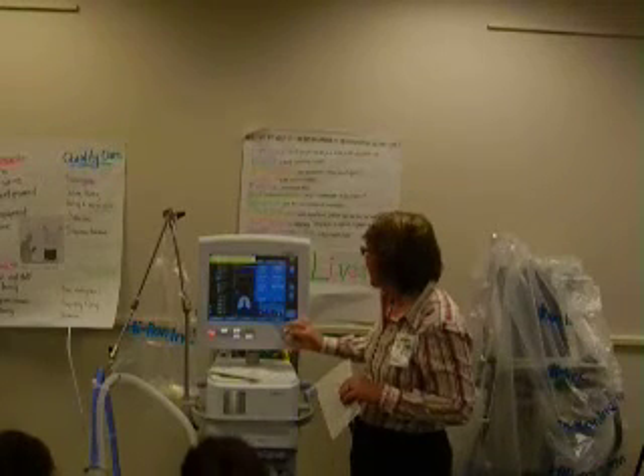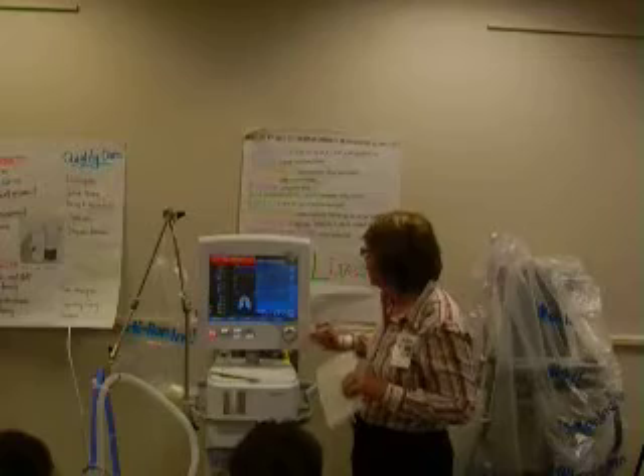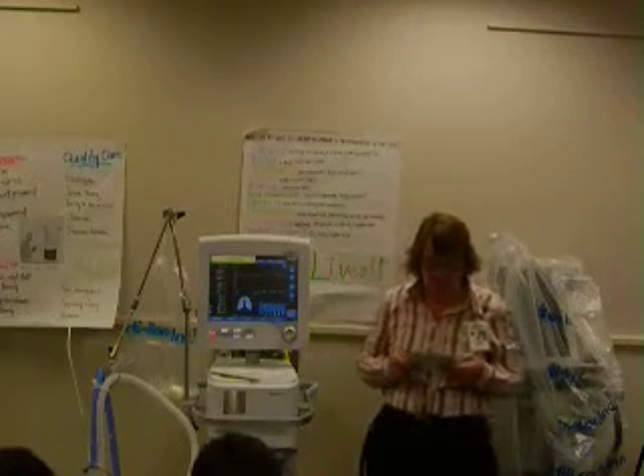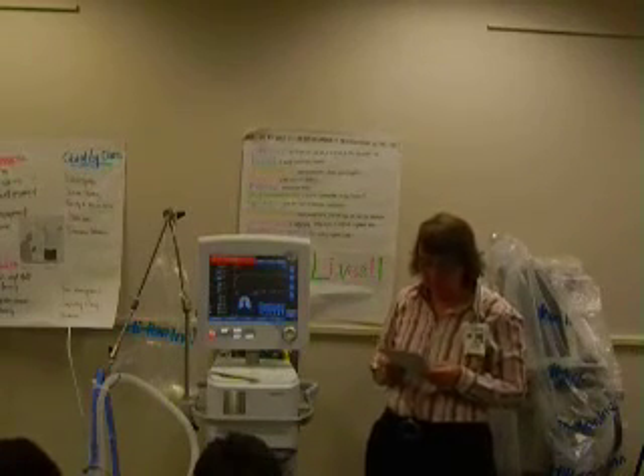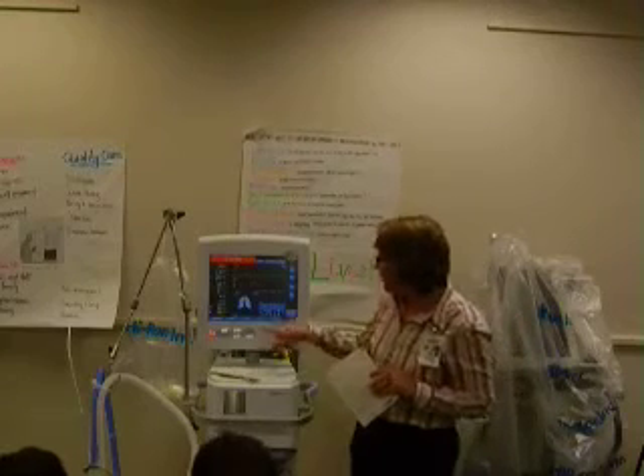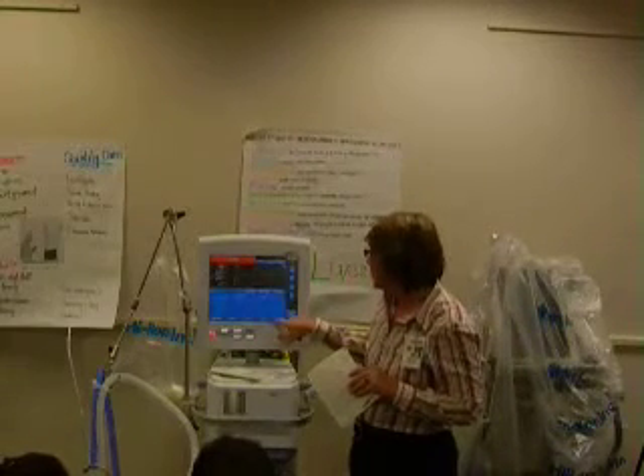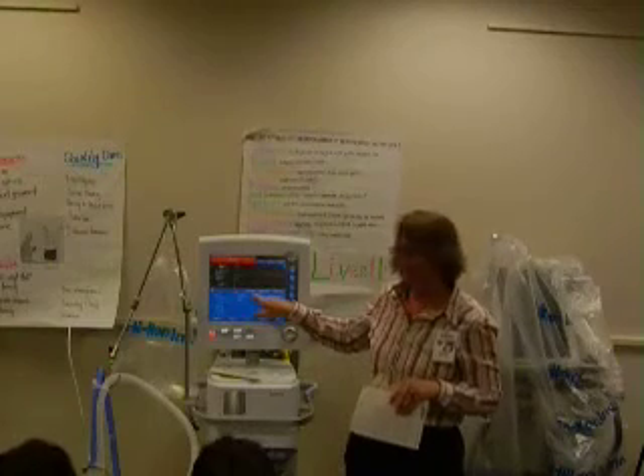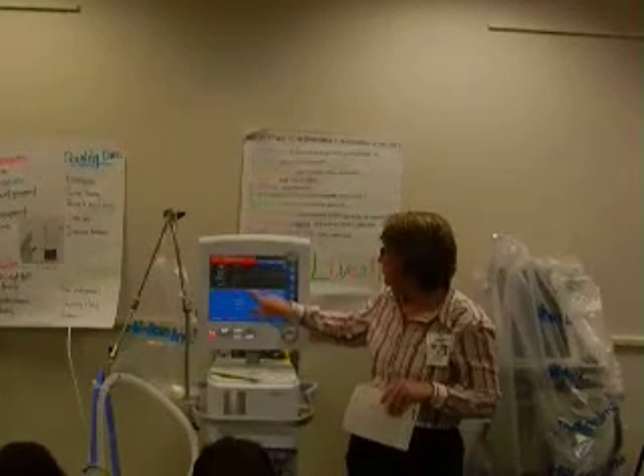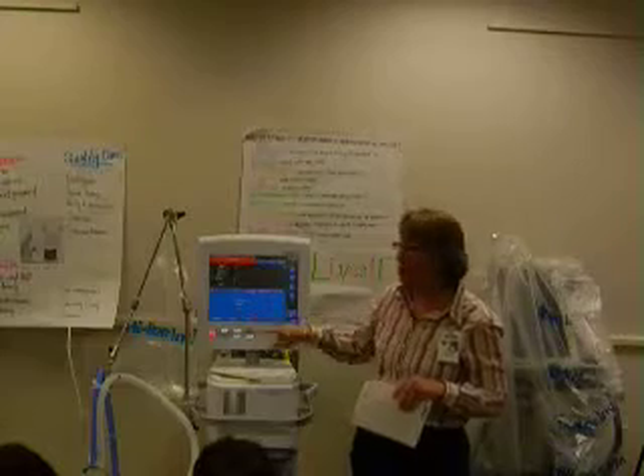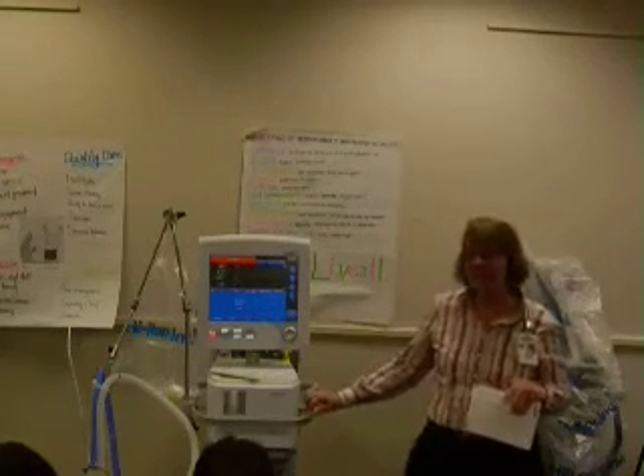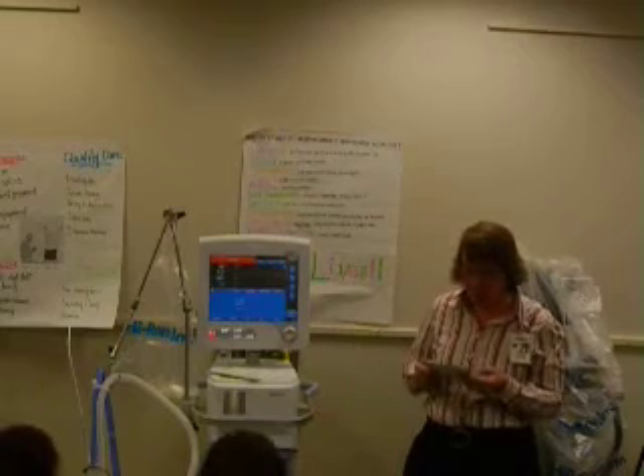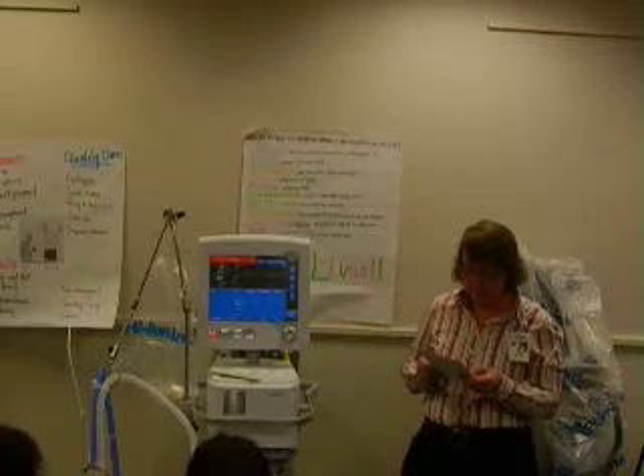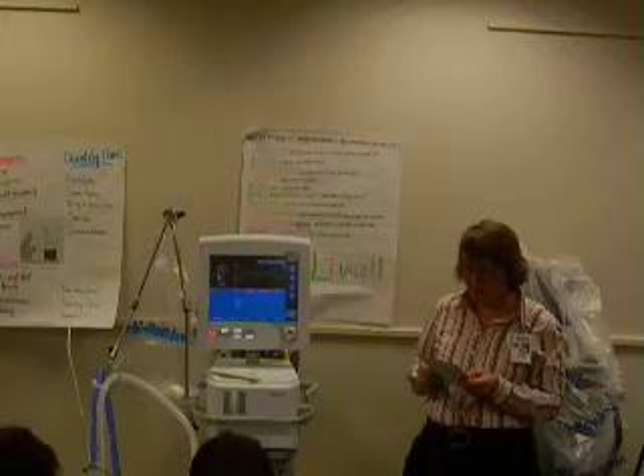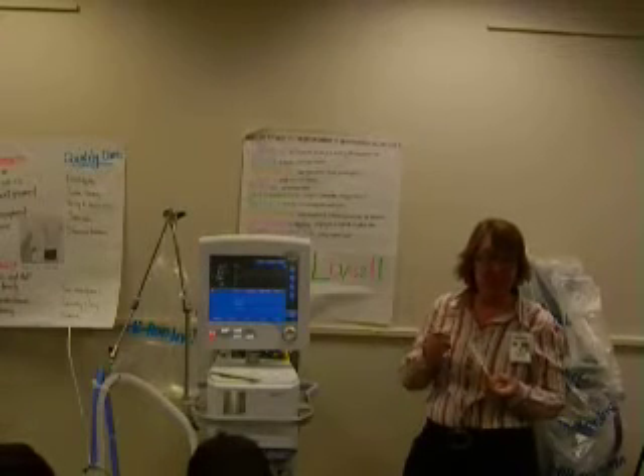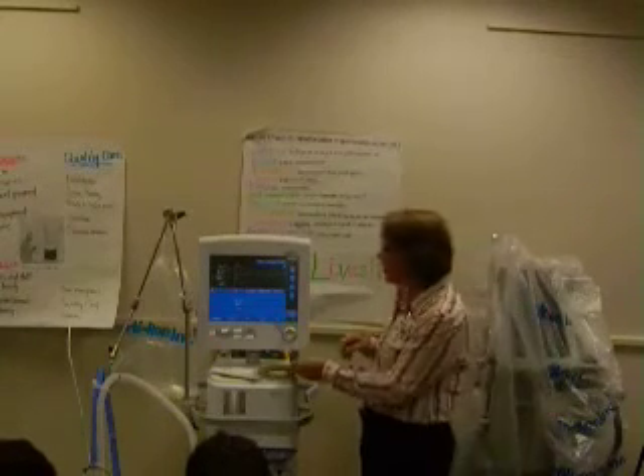So you need to be in SCMV. Now we're in there. We confirmed everything. Okay. So now we're going to do the flow sensor calibration. And to do that, we go to System and then Tests and Calibrations. And you'll see flow sensor, tightness, and O2 cell. We don't do the O2 cell unless it tells us we have to. So part of the calibration, you're going to see in the next step 6, it's going to say perform flow sensor calibration, tightness test, and if necessary, the O2 cell calibration. You just want to make sure that this has to pass.